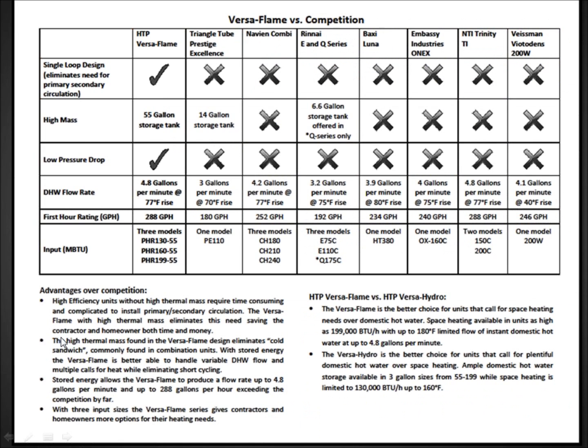VersaFlame versus the competition. You've got the Flame here, you've got the Prestige Excellence, the Navien Combi, the Rinnai, Baxi, Embassy, Trinity, and Viessmann. And as we go along, we're talking about hydraulic piping, what they have to do, as far as the mass of the system, eliminating buffer tanks, as far as pressure drop. I mean, we have no pressure drop because we're circulating through a large storage tank versus, as we well know, these low mass systems that require primary, secondary piping.